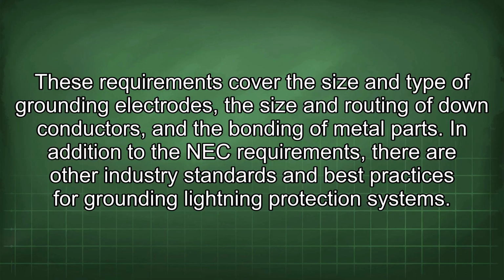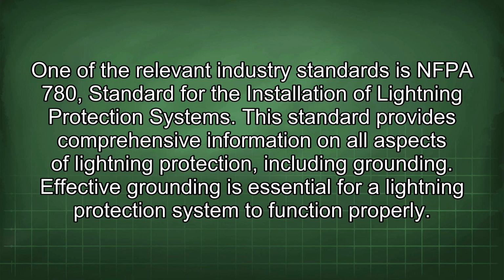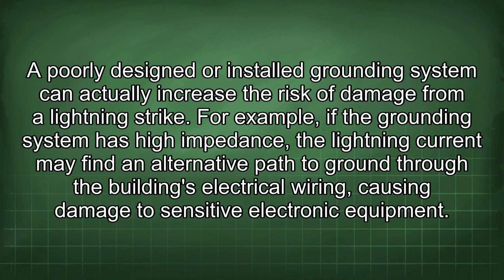In addition to the NEC requirements, there are other industry standards and best practices for grounding lightning protection systems. One of the relevant industry standards is NFPA 780, the standard for the installation of lightning protection systems. This standard provides comprehensive information on all aspects of lightning protection, including grounding. Effective grounding is essential for a lightning protection system to function properly. A poorly designed or installed grounding system can actually increase the risk of damage from a lightning strike.